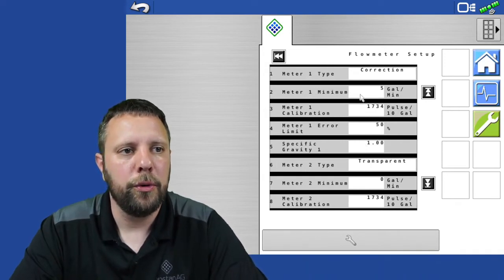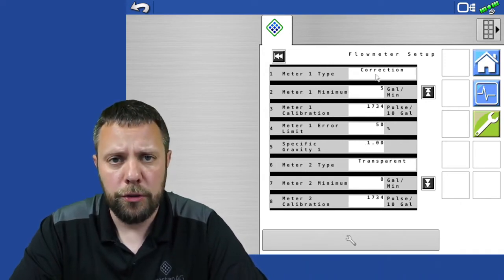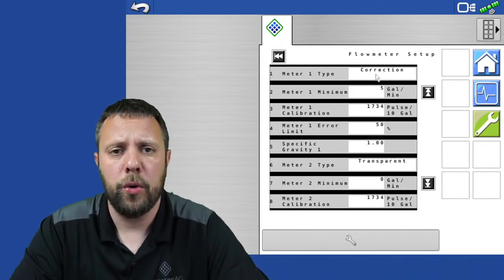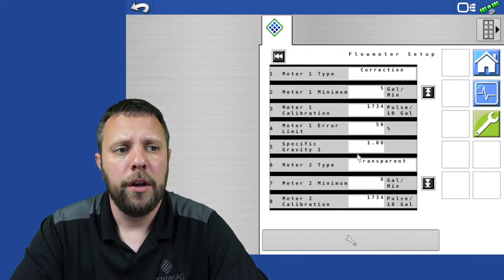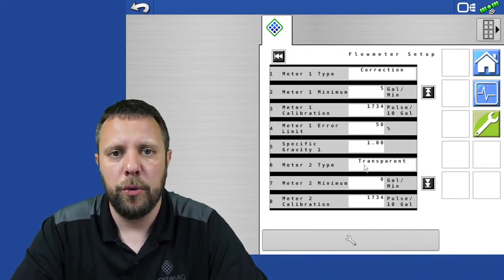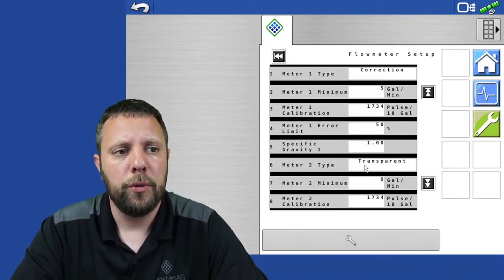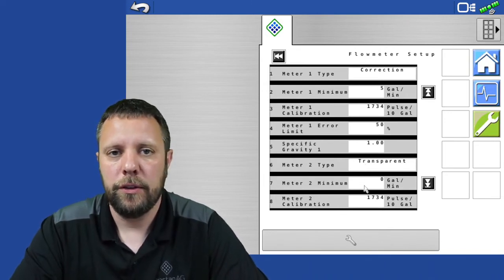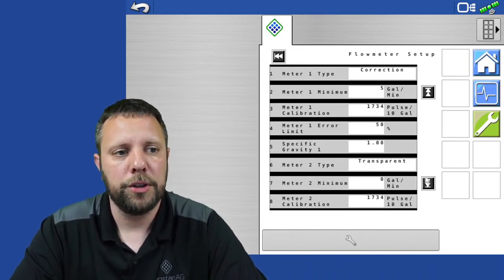Meter 2 type. Meter 1 type is your product flow meter, or the flow meter that's metering the product coming out of your boom. Meter 2 is always going to be your fill flow meter, so we always leave meter 2 as transparent type. It has a 0 gallon per minute minimum threshold.